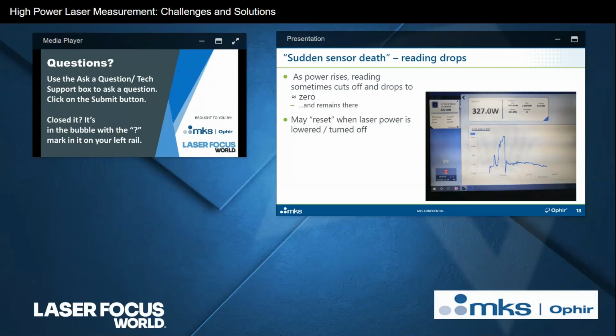one of two things often happens. One is that the sensor's readout suddenly drops down to 0 and remains there. Sometimes it drops down to 0 but doesn't remain there. Sometimes it goes back to looking okay if we turn everything off and try again a few minutes later, but then shortly thereafter it again drops down to 0. That's a nightmare. As anyone who's dealt with troubleshooting knows, problems that sometimes happen and sometimes don't, intermittent problems, are much harder to solve because they're obviously elusive. Once you can turn a problem on and off, then you've pretty much nailed it. So this sudden sensor death is one type of problem, one symptom, and there's a similar but different symptom.